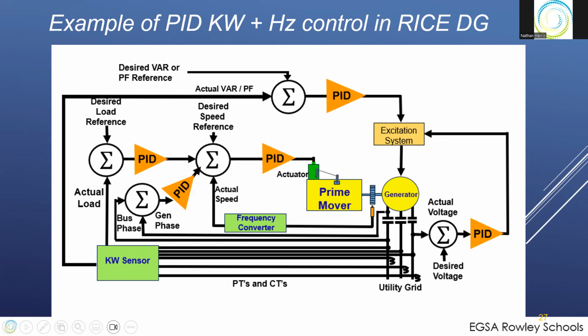As you start to bring in more power, say that you're going to synchronize across the breaker here, you have the two signals coming in, the gen phase and bus phase, and they're summed together. They drive another PID for your synchronizing that provides a speed trim signal to the speed regulator in order to bring it into synchronization. And once you're synchronized, then that one's turned off. The speed is kept there, but that's turned off. And once that's closed, now you're providing watts into your system.